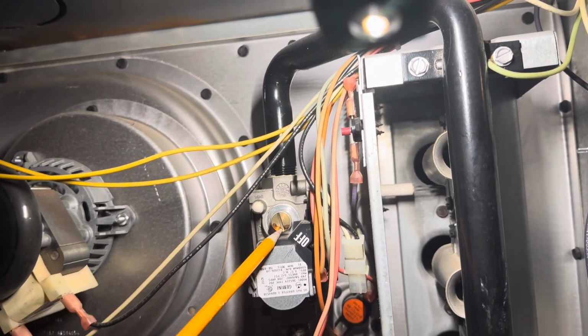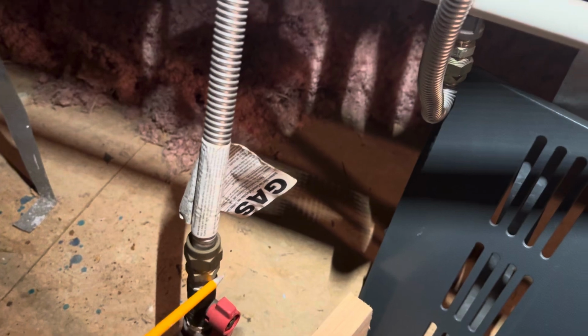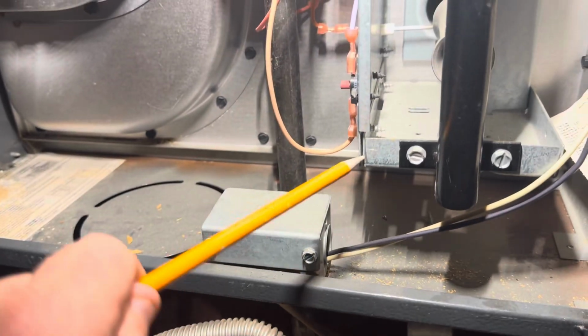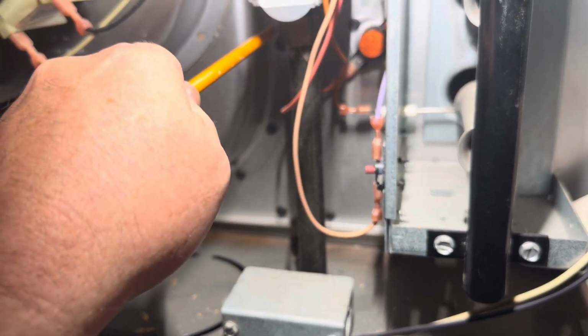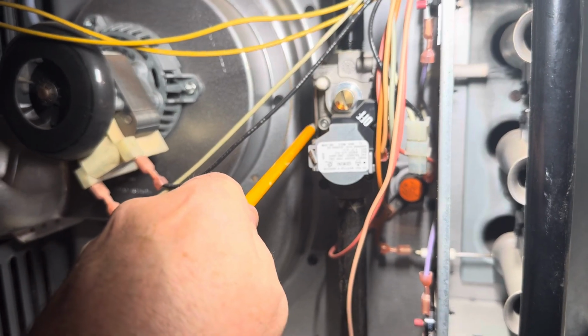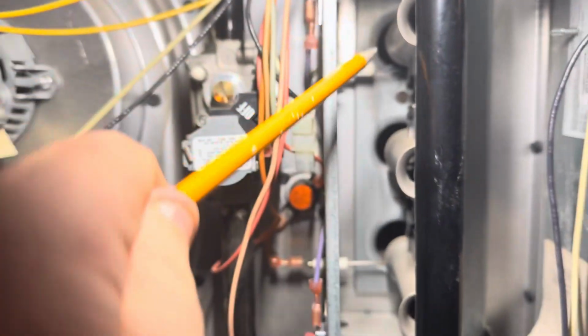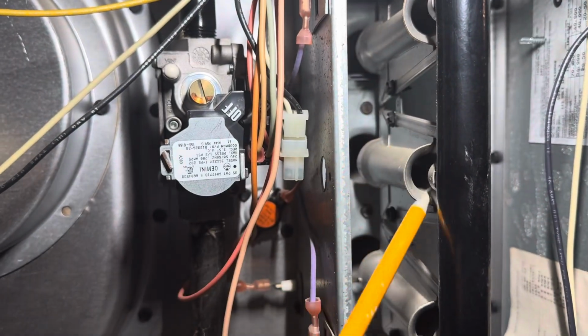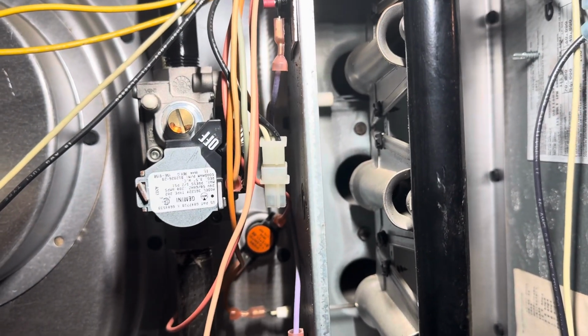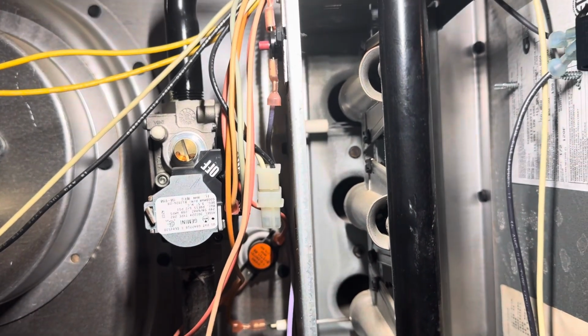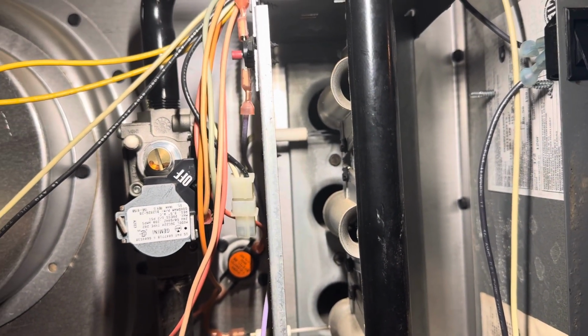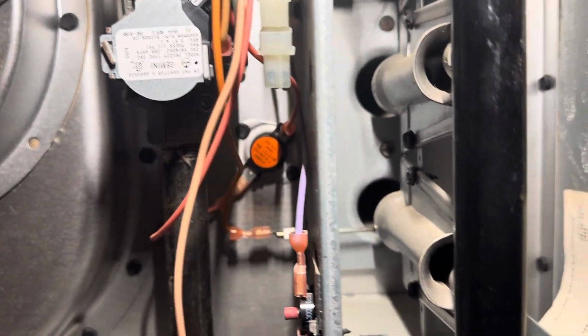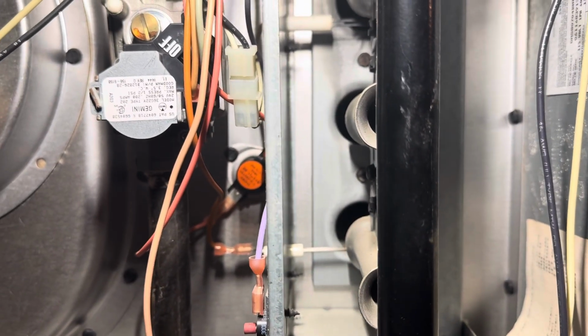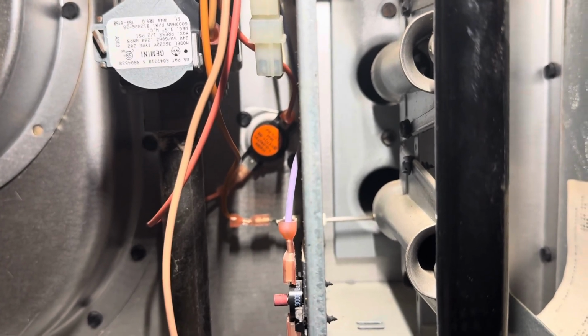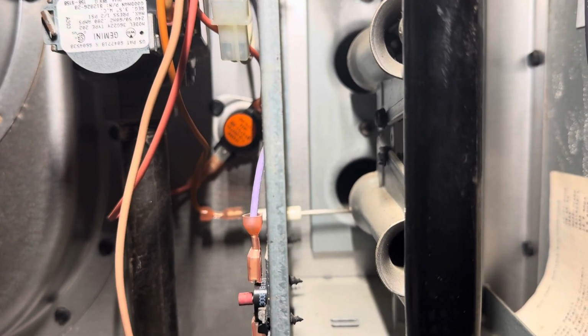next in the sequence, the gas valve, which if we look here, the gas is piped in. And here's our control valve. It comes up here, up into the valve. The valve opens and it sends the gas over here to the burners. And that's ignited. And then here at the bottom, we have what is called a flame rod or a flame sensor rod. And its job is important as well. It's a safety and it senses when there's flame.